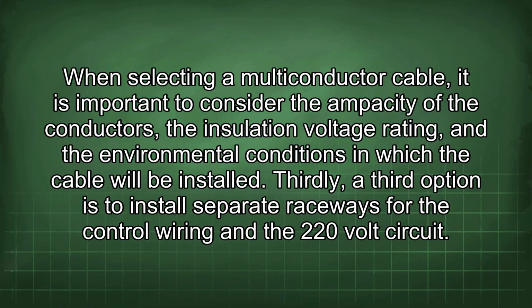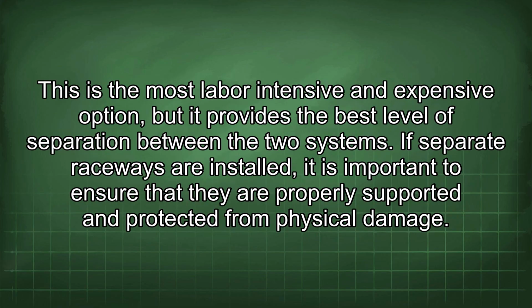Thirdly, a third option is to install separate raceways for the control wiring and the 220-volt circuit. This is the most labor-intensive and expensive option, but it provides the best level of separation between the two systems. If separate raceways are installed, it is important to ensure that they are properly supported and protected from physical damage.